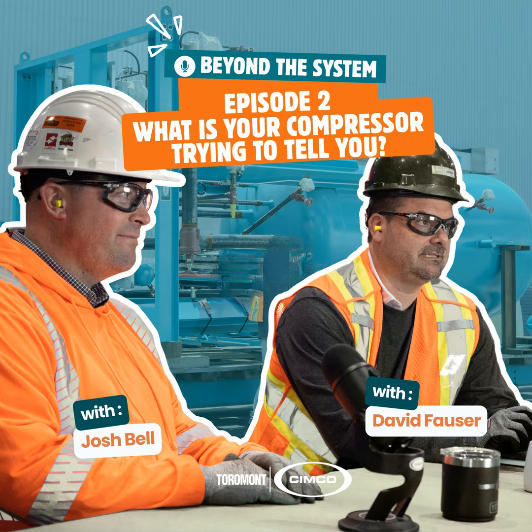One thing you want to make sure you have on hand is a good logbook, a good place to store records, and do very consistent readings. So on a reciprocating compressor, on any compressor, you're going to want to know your high pressure, your oil pressure, and your low pressure, and document them, because those may lead you to other challenges with your system. It may not always be a compressor issue, but those recordings will help get you there. Often they may have discharge temperature. Sometimes they do, sometimes they don't. Oil temperature is also another important number, usually not available on a smaller machine, but on the smaller reciprocating compressors, you'll usually have your cooling temperature.